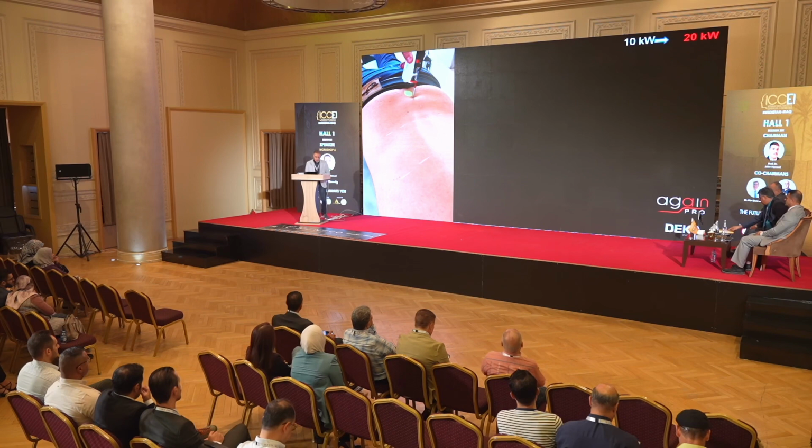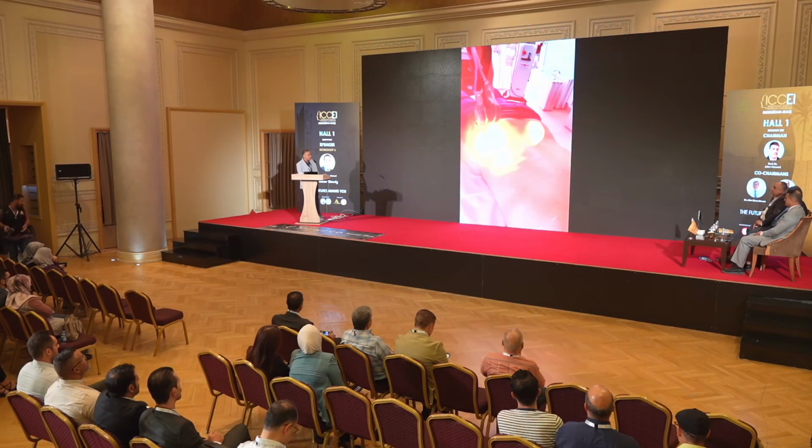This short video shows the 30 millimeter spot size, as you see here, and high frequency of 3 hertz, 3 pulses per second. It's recommended to use it for the back or chest because it's a wide area. It consumes many pulses and, as you know, consumes time.